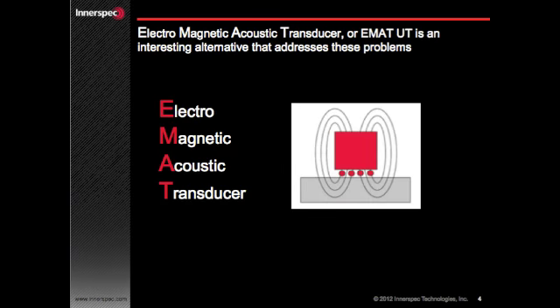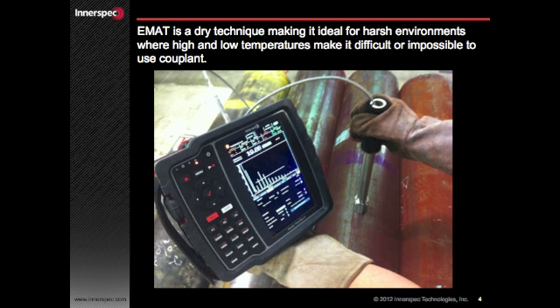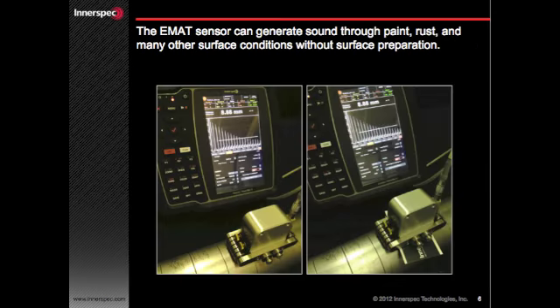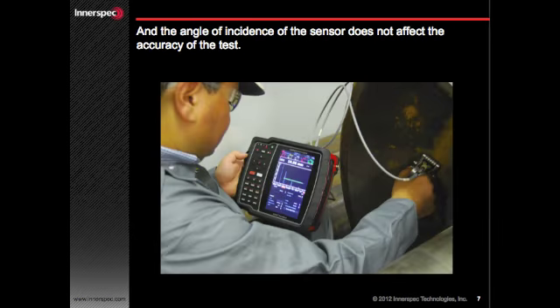Electromagnetic acoustic transducer, or EMAT, is an interesting alternative that addresses these problems. EMAT is a dry technique, making it ideal for harsh environments where high and low temperatures make it difficult or impossible to use couplant. The EMAT sensor can generate sound through rough, painted, and oxidized surface conditions without surface preparation. Additionally, the angle of incidence is not a factor, making EMAT ideal for curved and irregular surfaces, such as tubes and pipes.